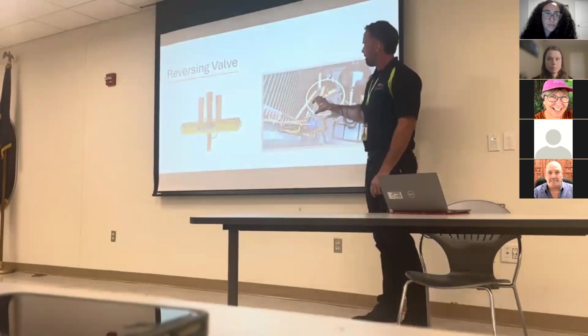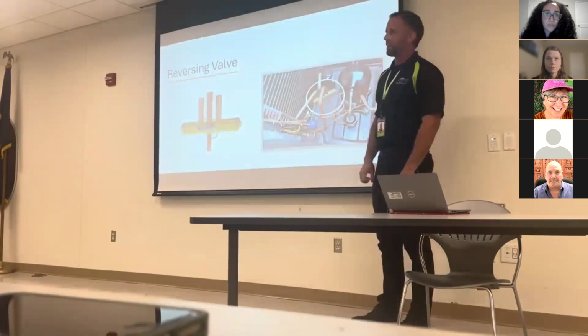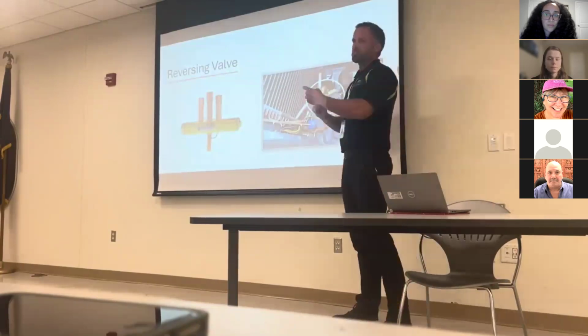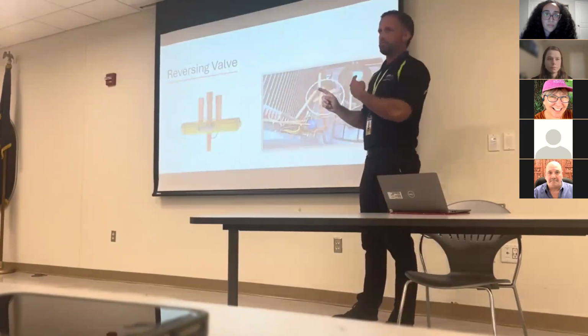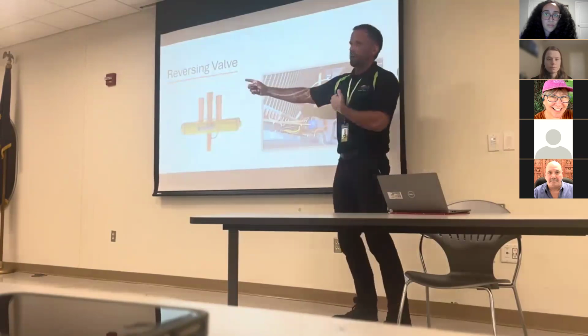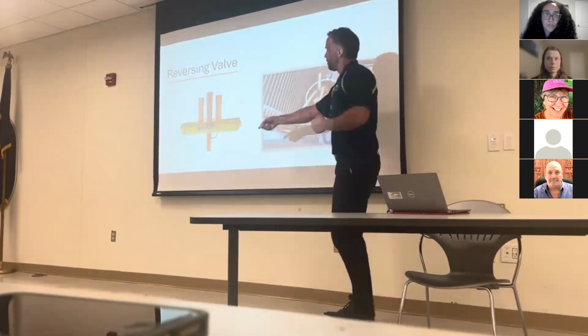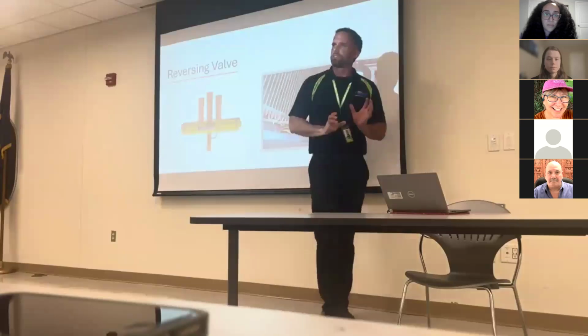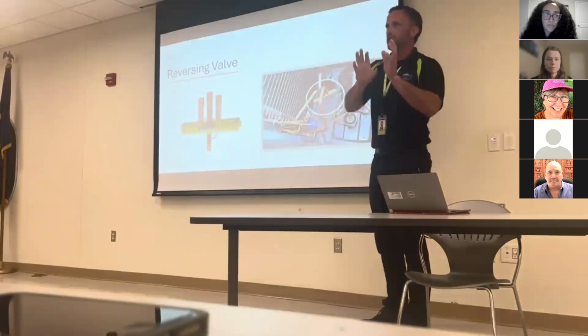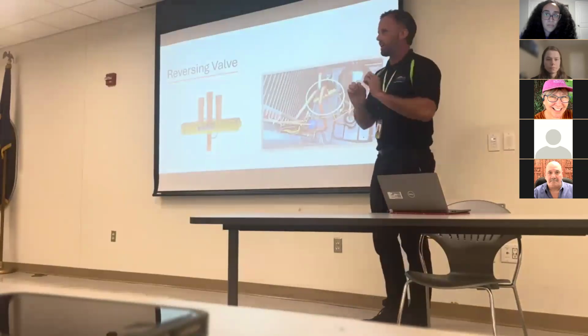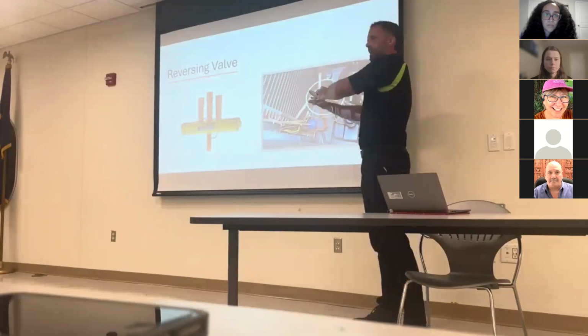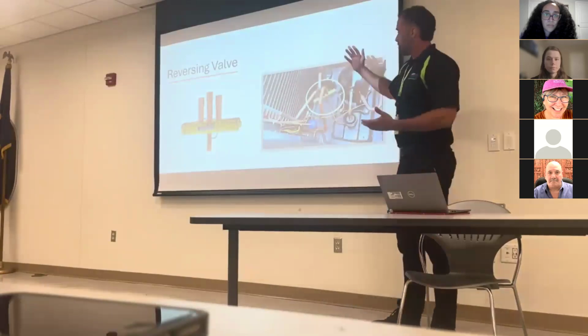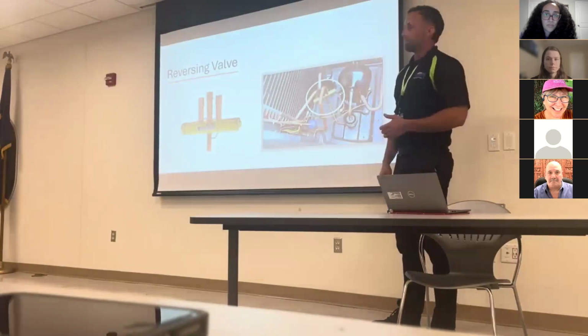Down inside of a heat pump, you'll find one part that's different than an air conditioner, called the reversing valve. That's actually the part that changes the direction of the refrigerant. It'll slide one way for heating, then that thing will slide over and push it out the other pipe for cooling. It just changes the direction of which way the hot gas is going to go - we're going to push the hot gas inside, or we're going to push the hot gas outside. Other than that, most of these parts are very similar to an air conditioner.